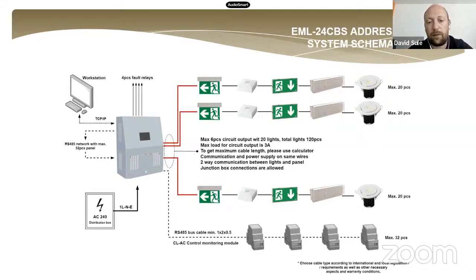The panel can be controlled by a maximum of 32 CLAC control monitoring devices. This device is installed in the General Light SubDB, and this module can be activated by AC230 failure and a normally open or normally closed signal. And this module communicates back to the panel, and the panel sends direct information to the address of any light which needs to be controlled by the sub-DB failure.